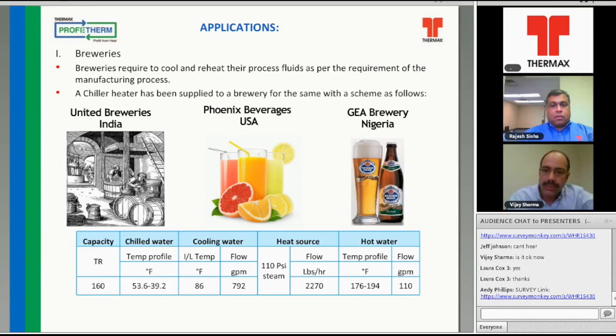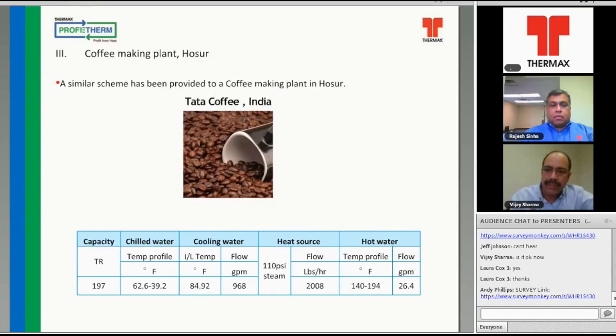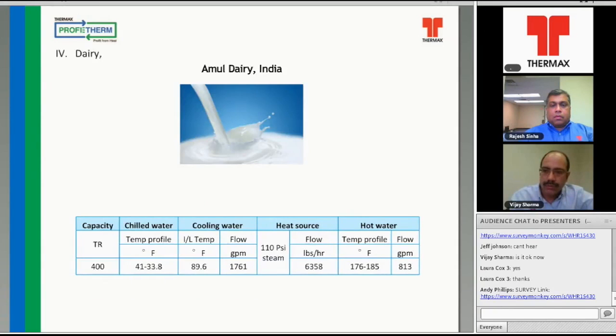So what advantage you get from absorption chiller heater is the hot water temperature can go as high as 195, while typically any other chiller heater has a restriction on the heating output. So the best thing here is the chiller is giving you a cooling of 39.2 as well as a heating output at a temperature of 194. So this is what the chiller heater is used for, as a simultaneous application from a single unit. Again, going to coffee, which is the same, giving chill water temperatures of 39 and hot water temperatures at 194. So coffee is one of the examples.